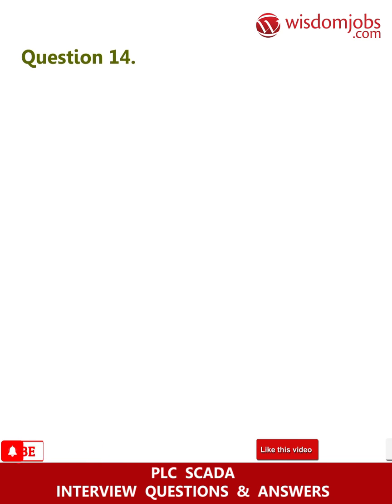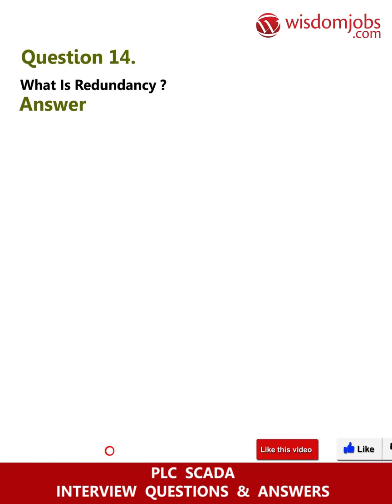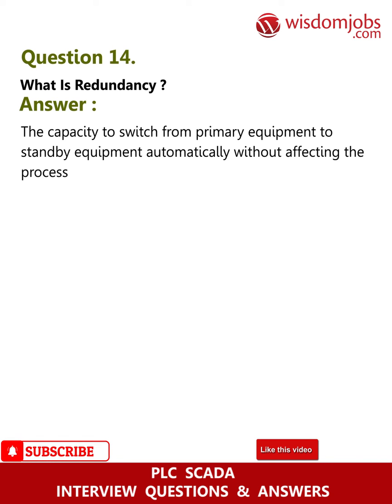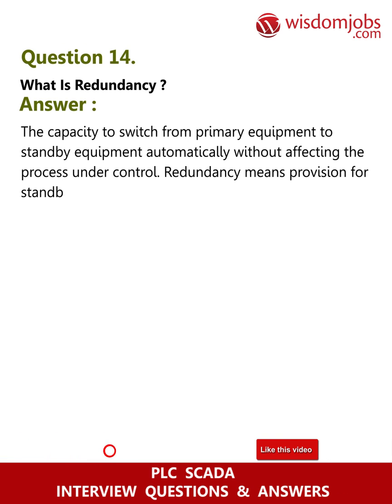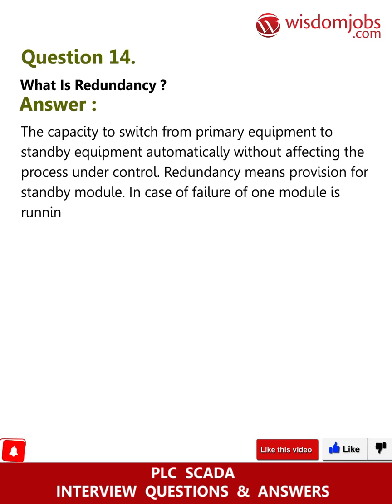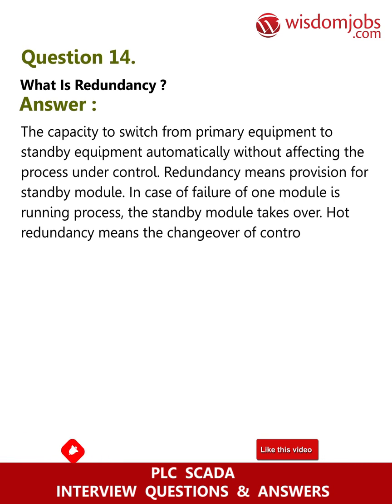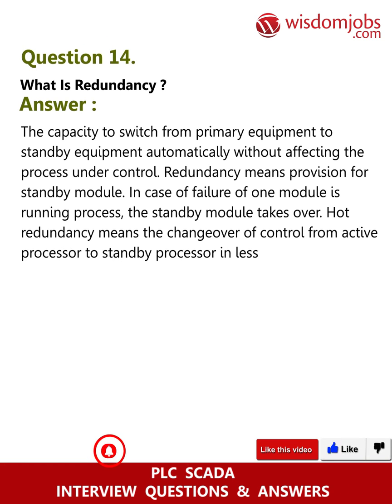Question 14: What is redundancy? Answer: The capacity to switch from primary equipment to standby equipment automatically without affecting the process under control. Redundancy means provision for a standby module in case of failure — if one module fails during a running process, the standby module takes over. Hot redundancy means the changeover of control from the active processor to the standby processor in less than one scan time.